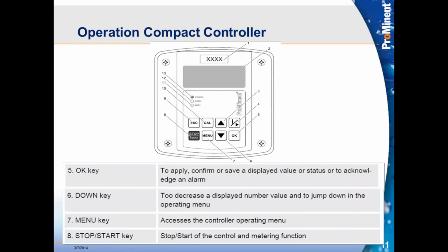We have an OK or an enter button. Once we've changed the parameter, to accept it or verify that that's what we wanted to change it to, we have to hit OK. We have a down arrow, just the opposite of the up arrow right above it. Menu key, so that's helping us scroll through. Start stop key to the left at the bottom. That start stop key will start or stop the control output. So if you're controlling a pump, even if that pump doesn't have some way to start and stop it, you can stop the control output by coming up to the unit and pressing the stop.